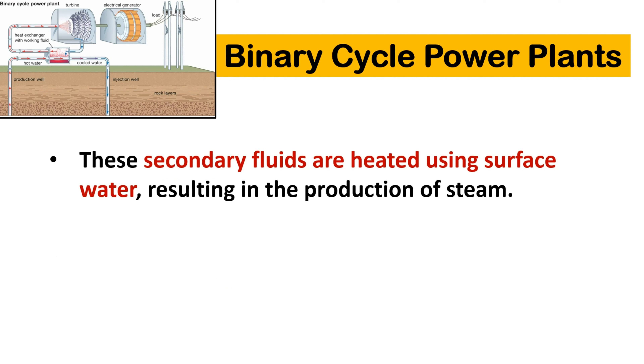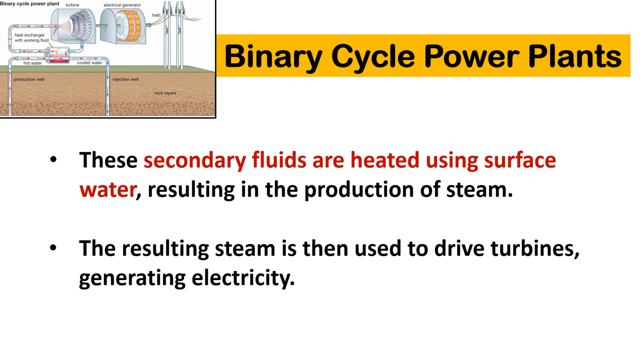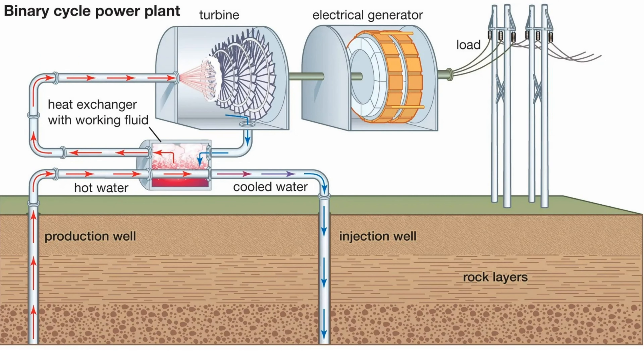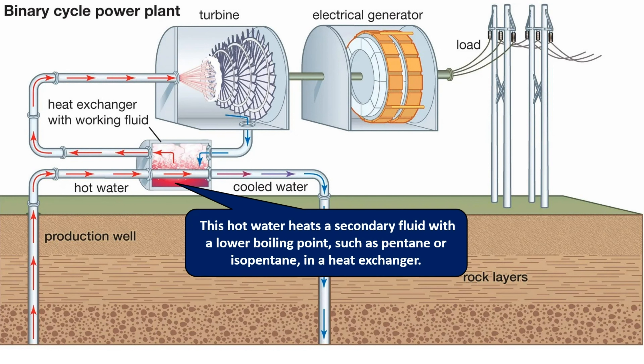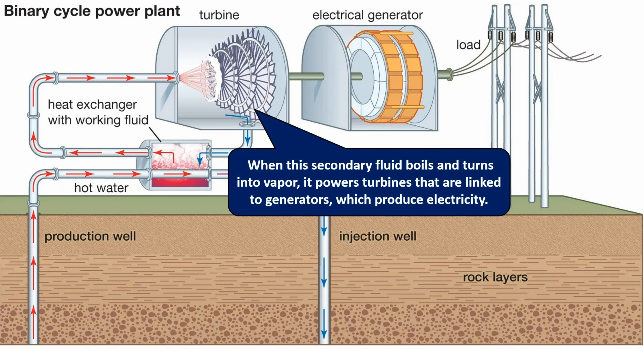These secondary fluids are heated using surface water, resulting in the production of steam. The resulting steam is then used to drive turbines generating electricity. Binary cycle power plants operate by pumping hot water from underground reservoirs to the surface through production wells. This hot water heats a secondary fluid with a lower boiling point, such as pentane or isobutane, in a heat exchanger. When this secondary fluid boils and turns into vapor, it powers turbines linked to generators which produce electricity.